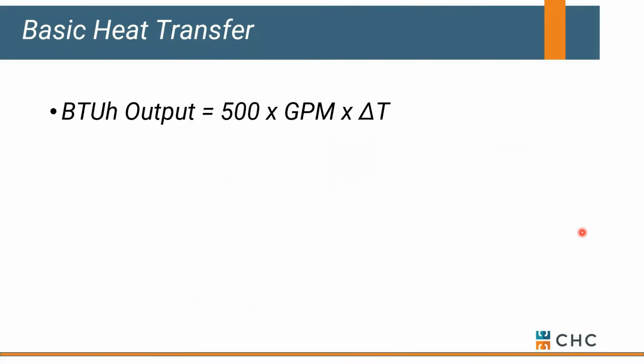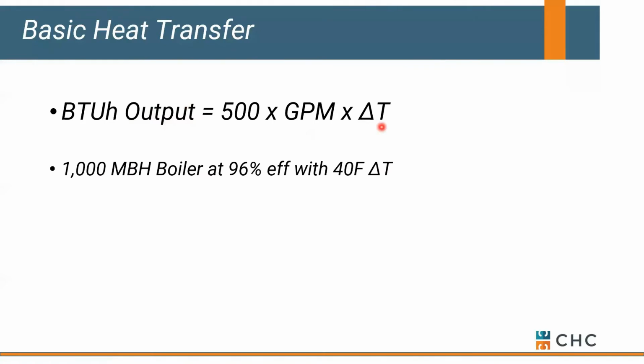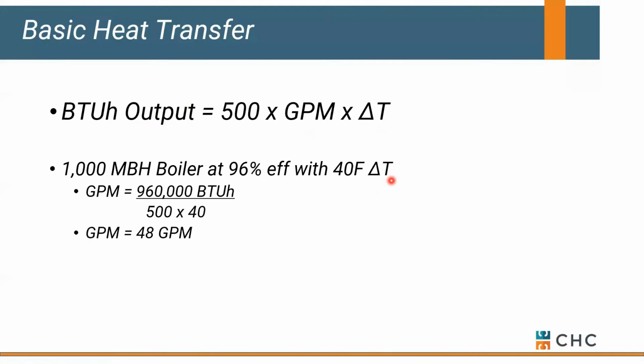We don't do a lot of math with boilers, but there is an equation that might help us a little bit. BTUs out of the boiler, or into our system, however you want to look at this, is equal to 500 as a constant times gallons a minute times delta T. This comes into play if we're trying to figure out how much flow we need across our boiler. If we've got it at high fire, and we might be designing for a 40-degree delta T across our boiler, so coming in at 100, leaving at 140, we can use this equation to figure out we need roughly 48, 50 gallons a minute of flow across this boiler in order to transfer heat at full fire at a 40-degree delta T, okay?